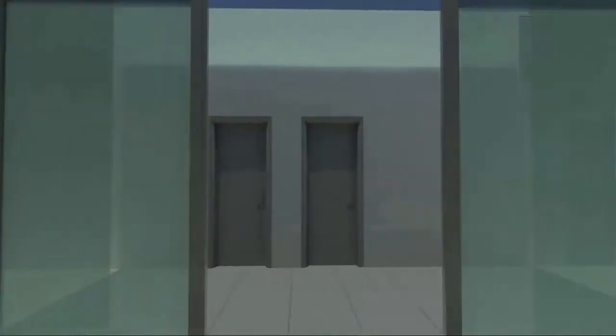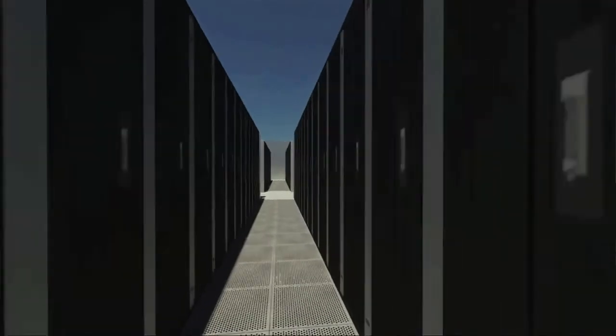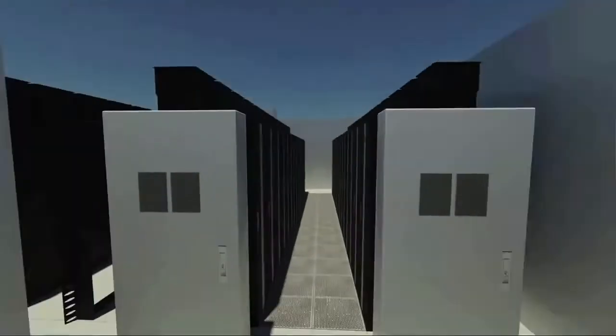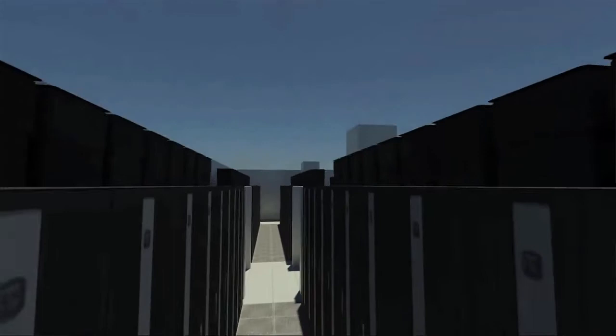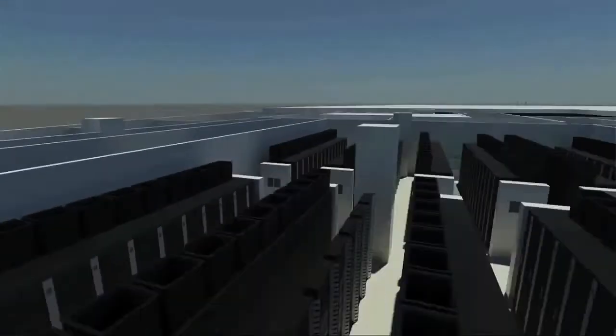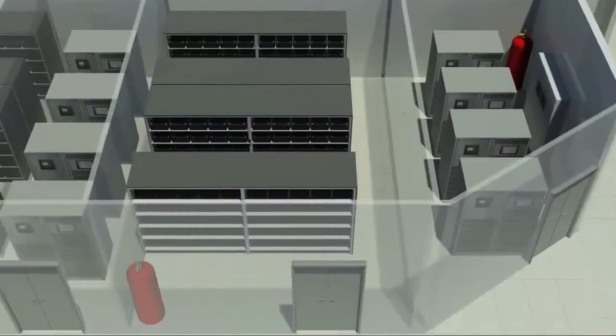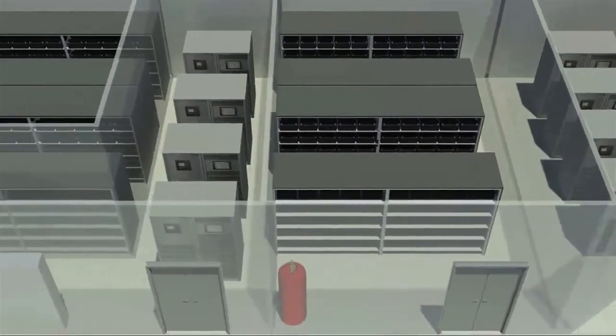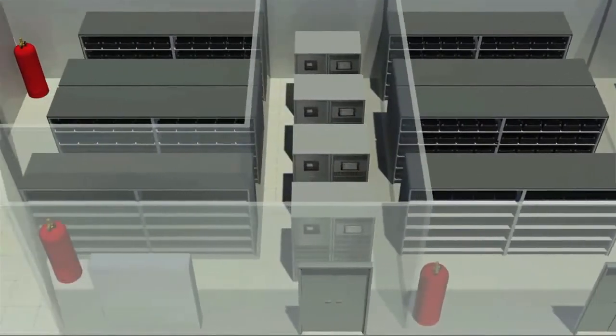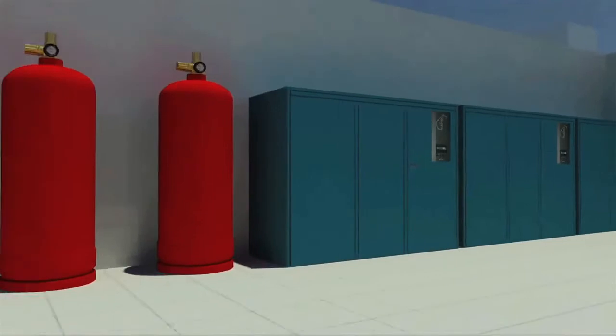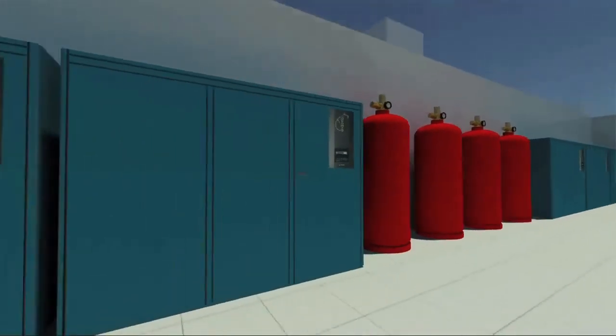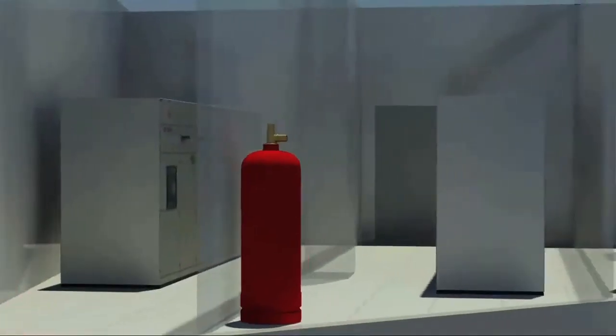From the Schneider side, all our ACs, the flooring, the LV panels, the main panels, the UPSs, everything was done by Schneider with their help. The software we're running is from yourselves, the DCIM. The whole facility is built on a tier 3 scenario, except on the power and cooling side, where we're actually on 2N, which is tier 4. When Oman eventually gets a second carrier, we'll be a full tier 4 scenario. We've certified the data center as tier 3 design with Uptime, and it's been operational since March, and so far it's going really well for us.